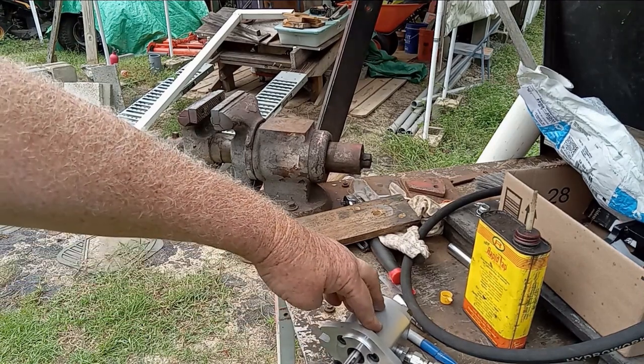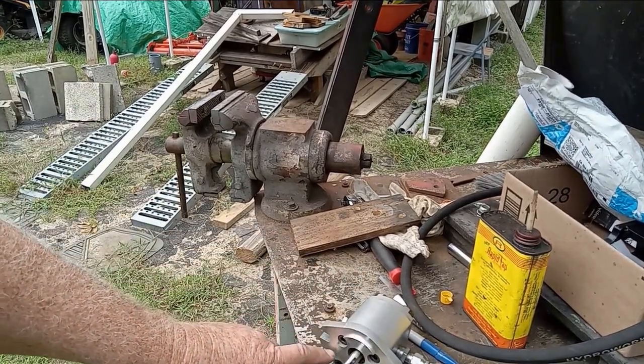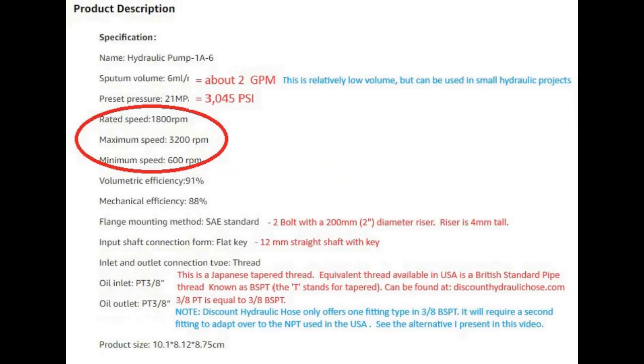I'll also be as specific as I can on a spec sheet. For example, this piece on the flange is two inches - you need a two-inch hole for that mount flush. This pump is about a two-gallon-per-minute pump. It's a relatively low-volume pump, but it can be used in small hydraulic projects. Maximum pressure is 3,045 PSI. Rated RPM speed would be 1,800 RPM, maximum speed 3,200 RPM, and minimum speed 600 RPM, giving you a wide range of RPM selection.